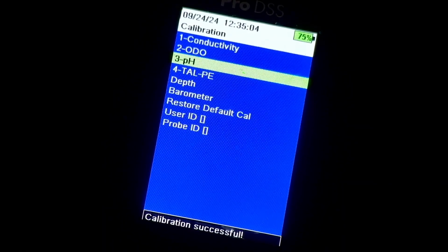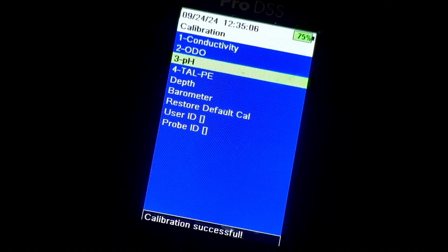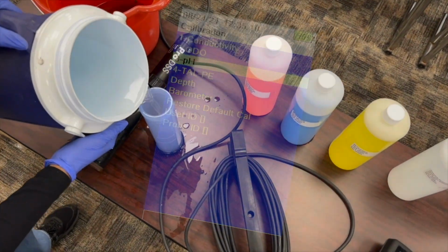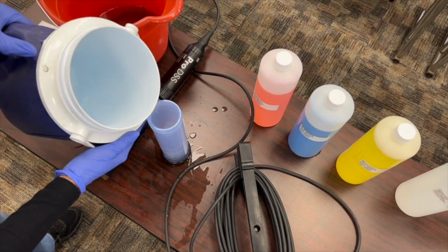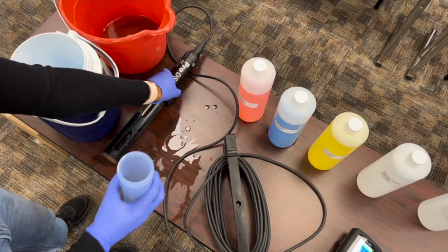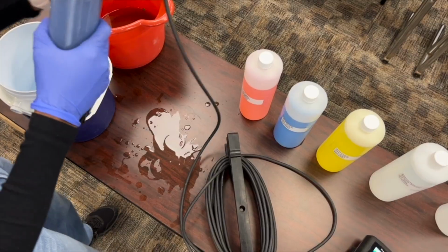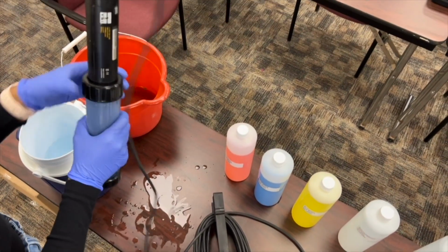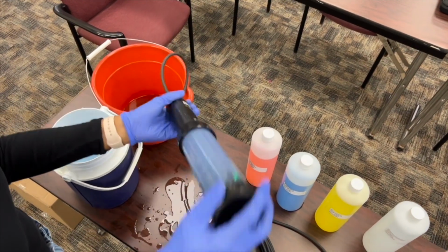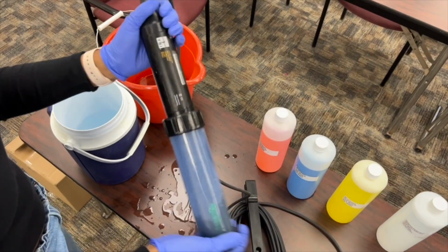Now we will move on to the yellow buffer for pH 7.00 to mimic neutral conditions. At this point, you can click the Escape button to get back to the home screen. Discard the blue buffer that was used, and then rinse the calibration cup and its sensors.